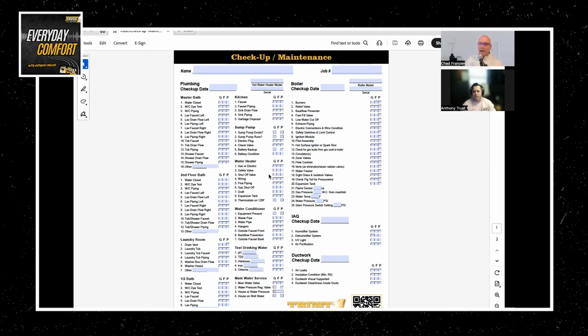Switching to boilers, I see things on this list like relief valves, low water cutoffs, and expansion tanks. What role do those play in keeping a system safe? Yeah, so with any type of heating system or even cooling systems, there's safety devices that are connected to each system. For a boiler, a relief valve is designed to relieve pressure if there's an issue. So most relief valves for a hot water system are 30 pounds of pressure. So if there's more than 30 pounds of pressure, that's going to let off excess pressure. It's actually doing what it's supposed to do.